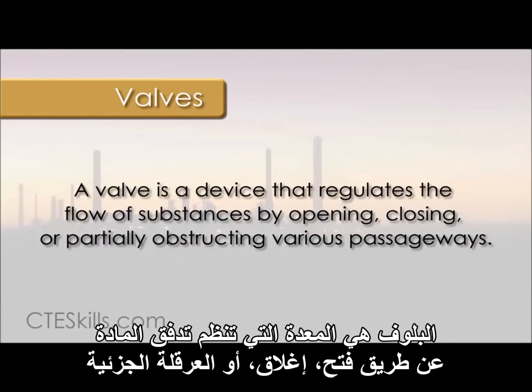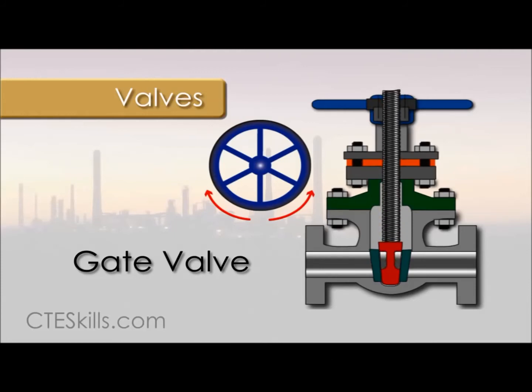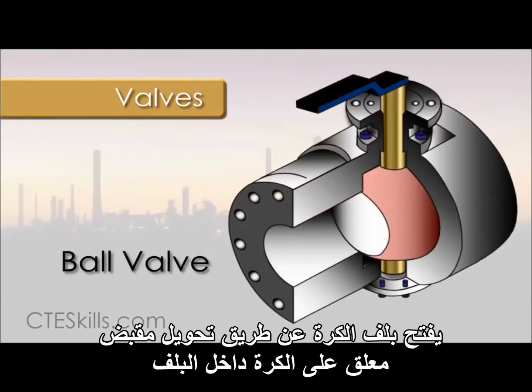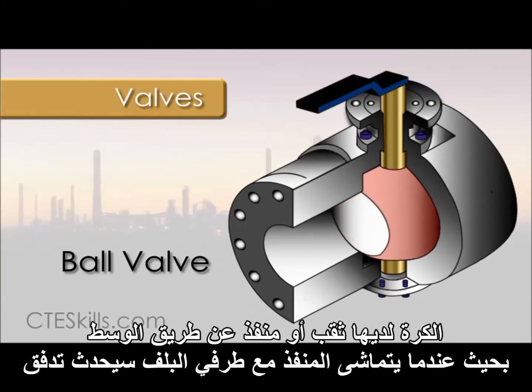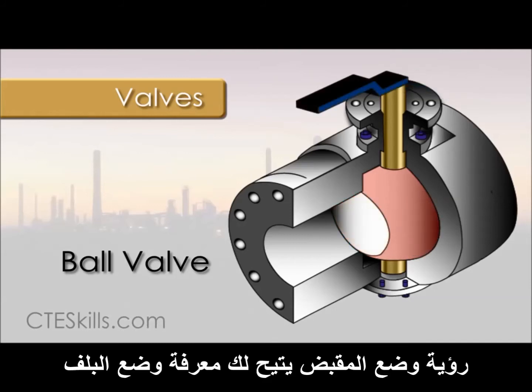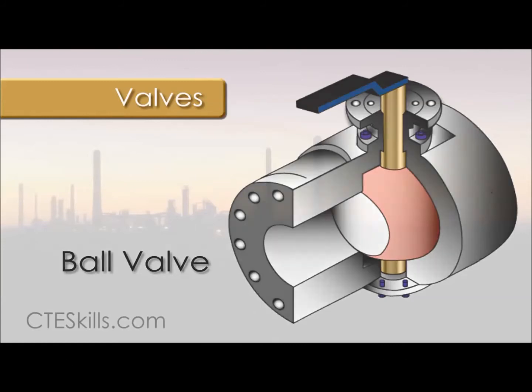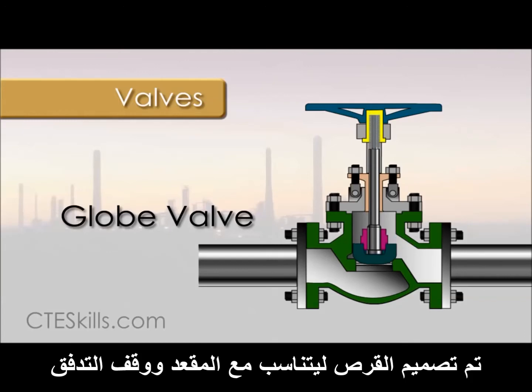A valve is a device that regulates the flow of substances by opening, closing, or partially obstructing various passageways. A gate valve is a valve that opens by lifting a round or rectangular gate or wedge out of the path of fluid. A ball valve opens by turning a handle attached to a ball inside the valve. The ball has a hole or port through the middle, so that when the port is in line with both ends of the valve, flow will occur. When the valve is closed, the hole is perpendicular to the ends of the valve, and the flow is blocked. The handle position lets you see the valve's position. A globe valve places a movable metal disc in the path of the process flow. The disc is designed to fit into the seat and stop flow.